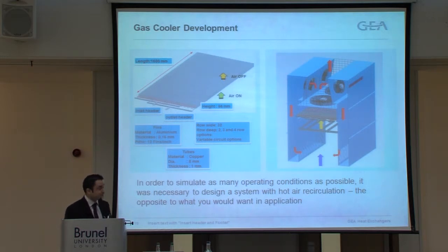One of the big advantages of this test setup was that we could change the coils in there. So in this case, we were measuring with a 2, 3 or a 4 row deep coil, and in some cases, as the analysis was being completed, we could take the coils away, modify them, change them, possibly manufacture them again, and put them back in. It also allows a lot of future opportunities, and although this project's coming to an end, Brunel will still be using a gas cooler in their test facility, and as GEA continues to advance its tube fin configurations, we can then put the coils back in here and see how they're operating.